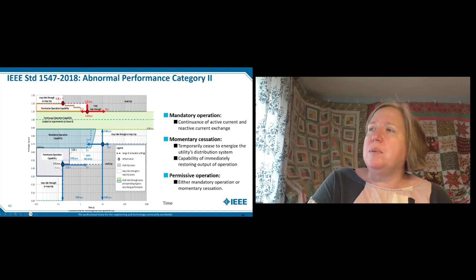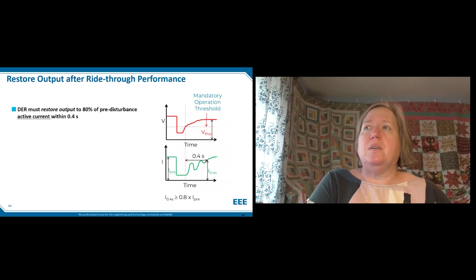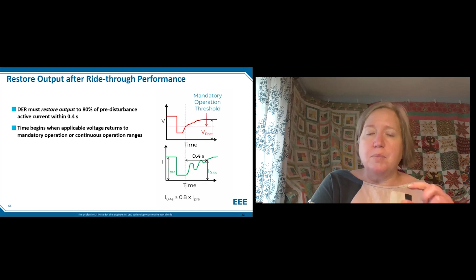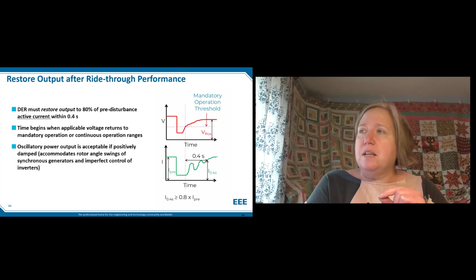So, restore output after the ride-through performance. DER must hit 80% of the pre-disturbance active current within 0.4 of a second. It applies when the voltage returns to mandatory operating or continuous operating ranges. So when the voltage comes back up to a good point, it's got that 0.4 of a second to get back up to 80%. It does not have to be steady power. It can oscillate if it's positively damped.